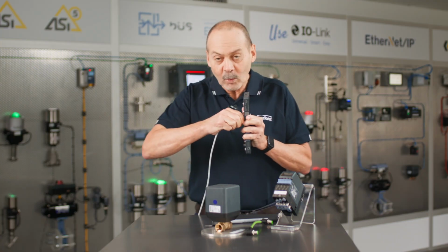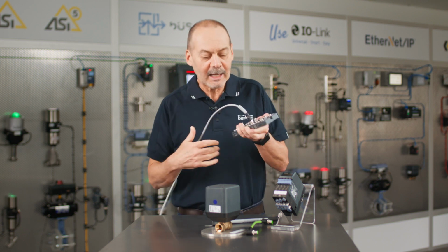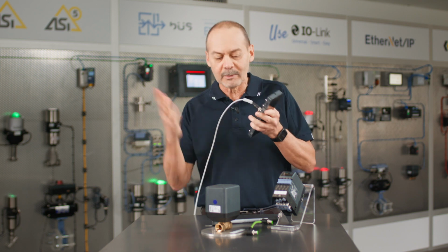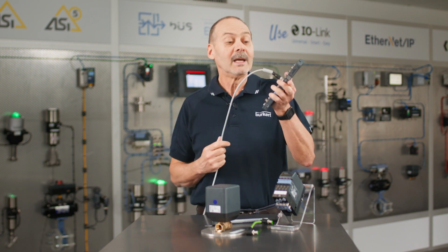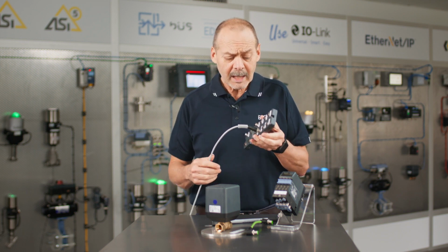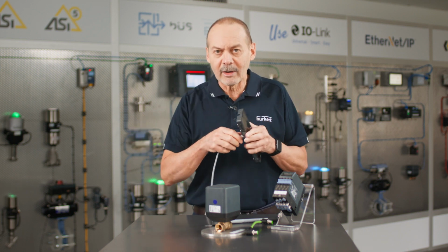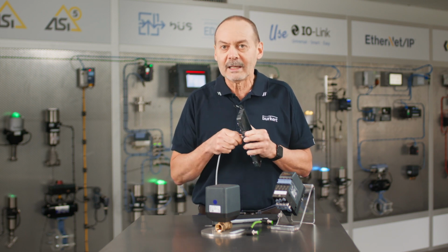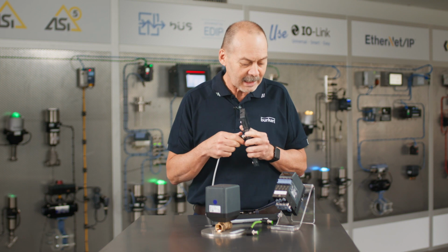Now, the issue is we hand tighten and we say that's done. So that's the way most people do their M12s, because they call them quick connects. We can do them with our hands. The problem is you've not engaged the O-ring that's inside. Other people will turn around and use a spanner on there, and what they'll do is they'll engage that O-ring for sure, but they'll actually crush it, and it may seal this time, but may never seal again.